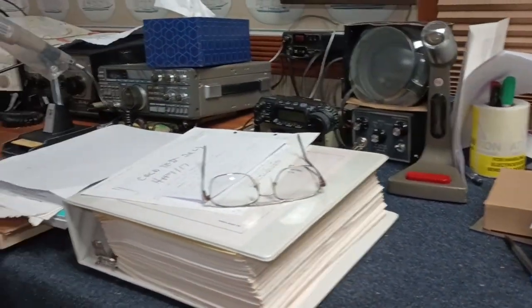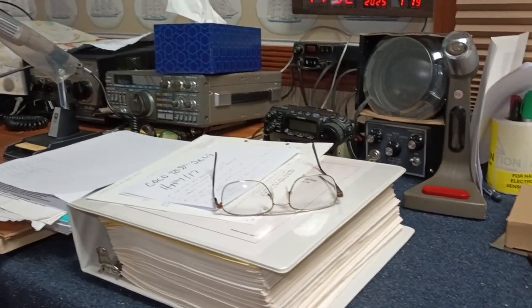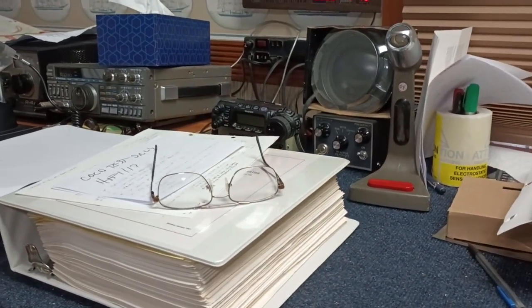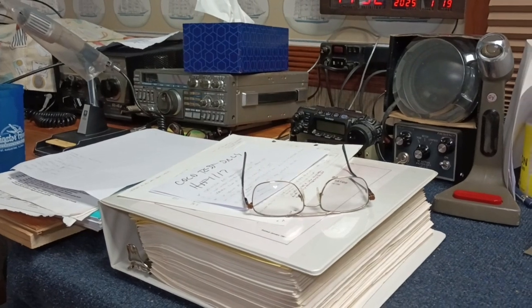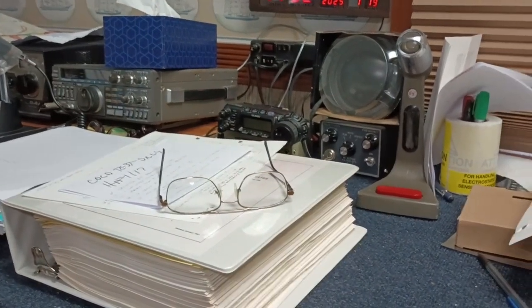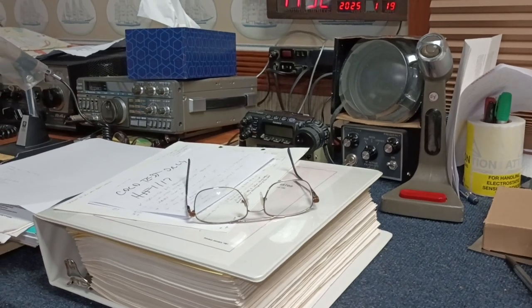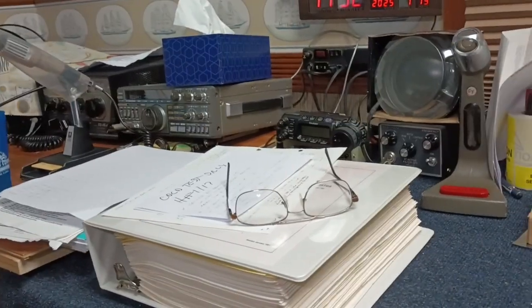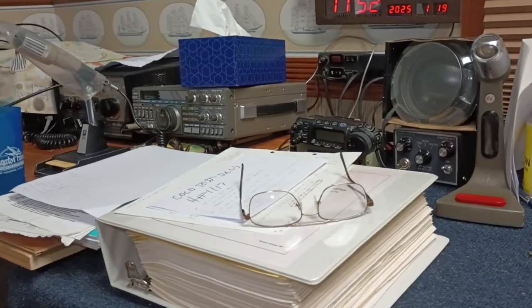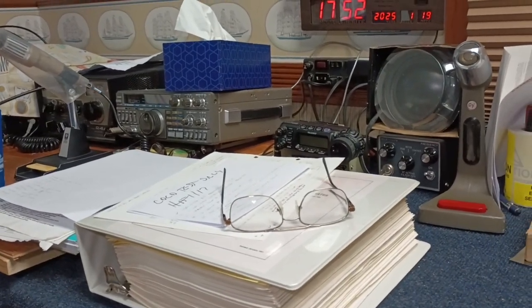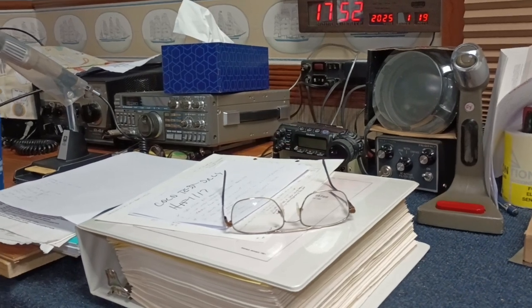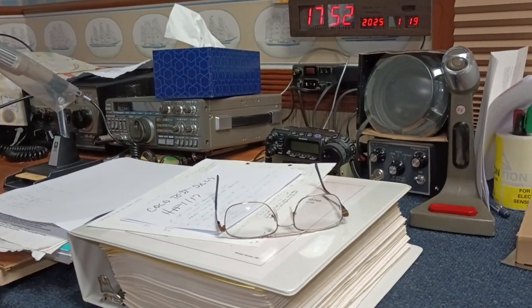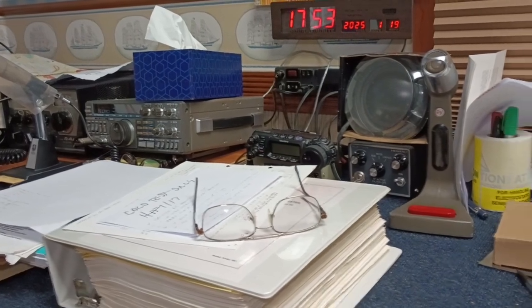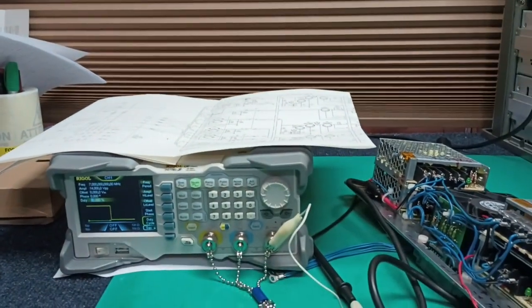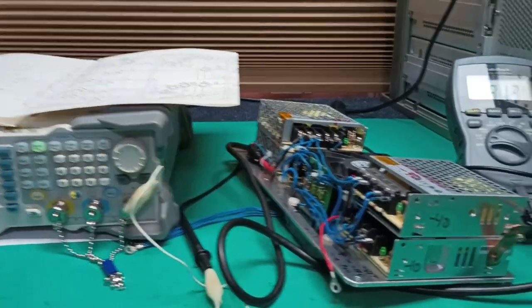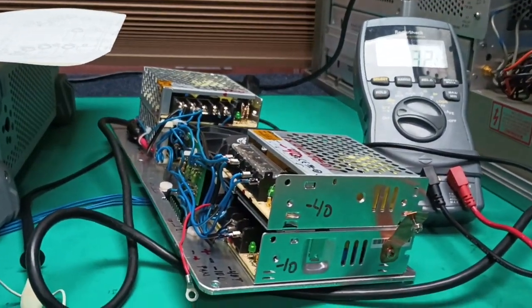Let's say there's equipment down here. I have the Yaesu rig connected to the other rigs for keying. It's been practiced to connect them together to eliminate voltage that exists between the two. There are problems with that in that connecting that together then allows for current flow instead of having a voltage difference. That can be a problem to iron out.